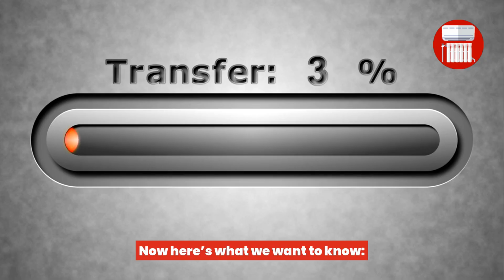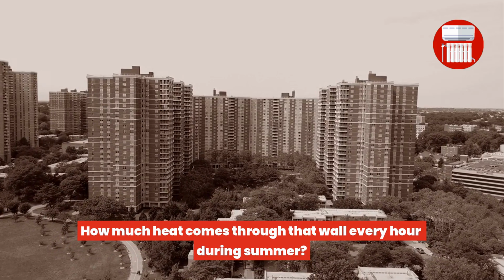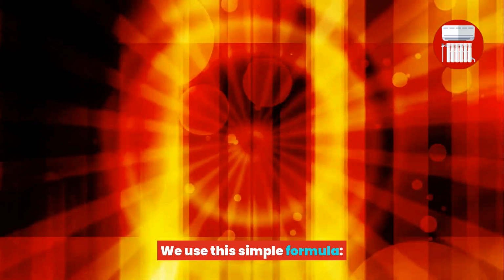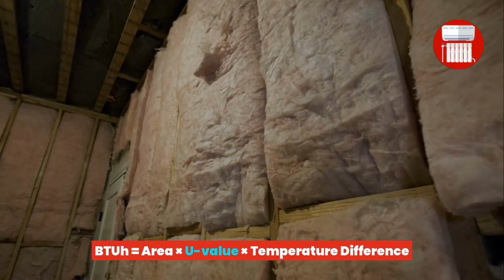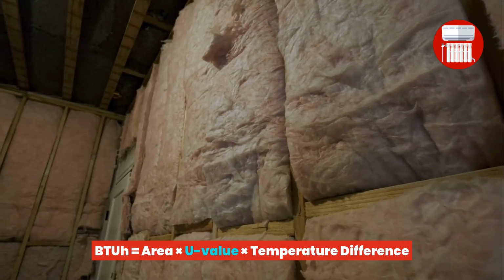Now here's what we want to know. How much heat comes through that wall every hour during summer? We use this simple formula. BTUH equals area x U value x temperature difference.